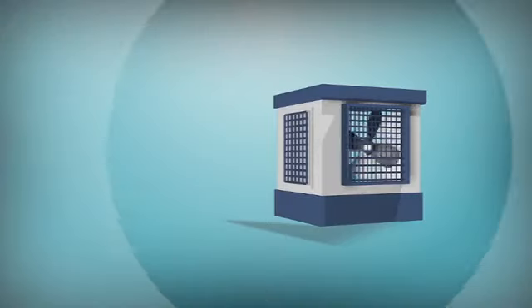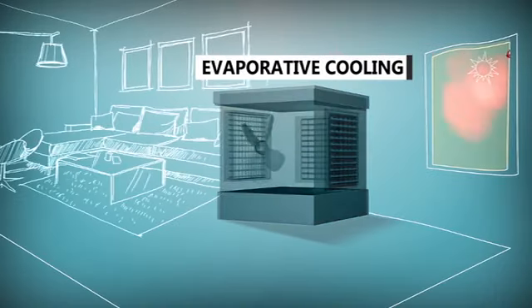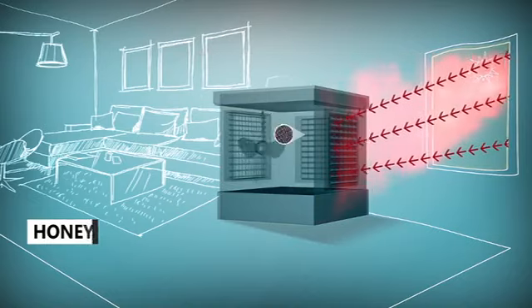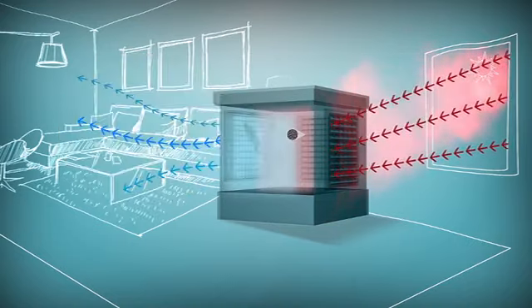But before we speak further on Tri-Cool Air Coolers, let's understand how air coolers work. An air cooler works on the principle of evaporative cooling. Hot air passes through a wet medium honeycomb due to which water vapors evaporate into the air and is blown forward using the fan.